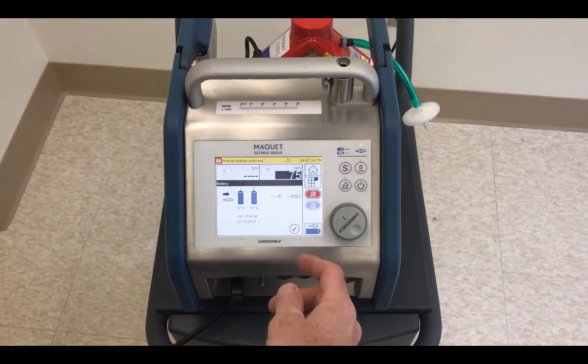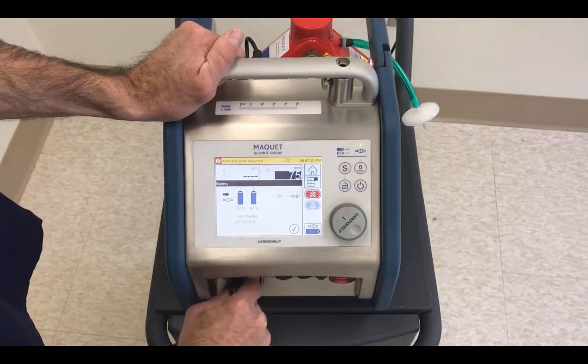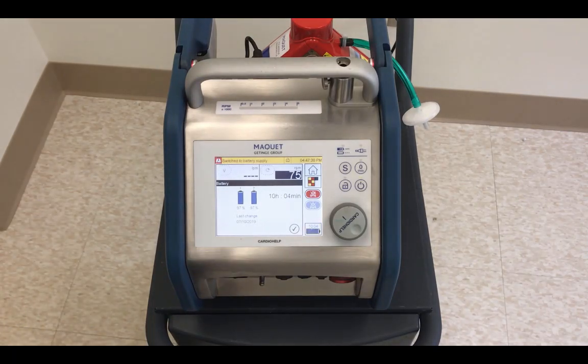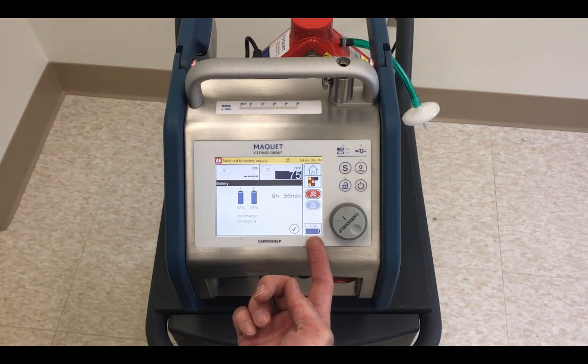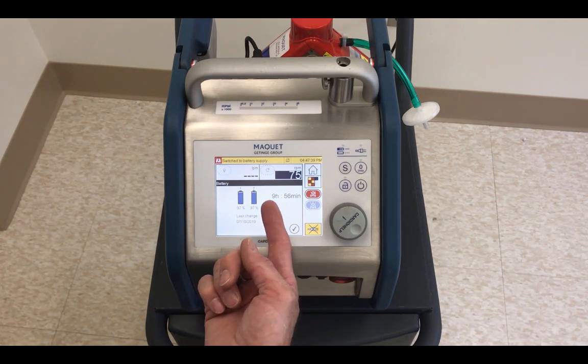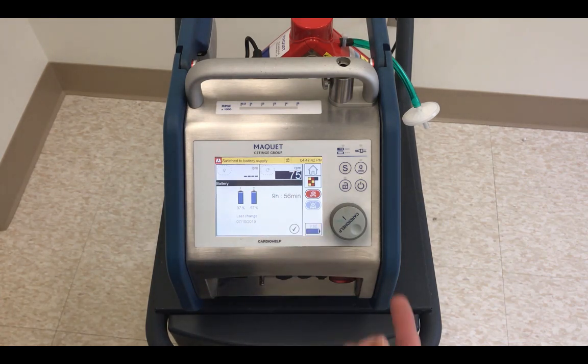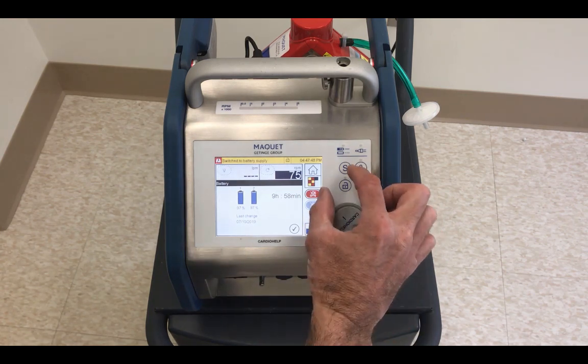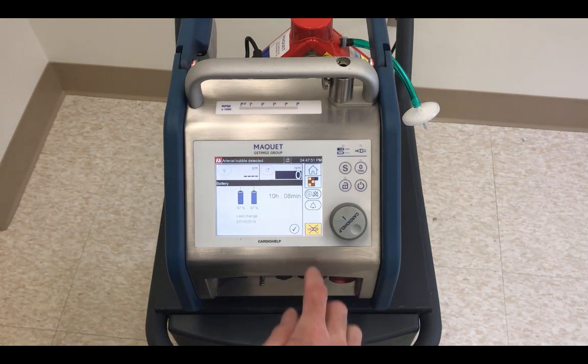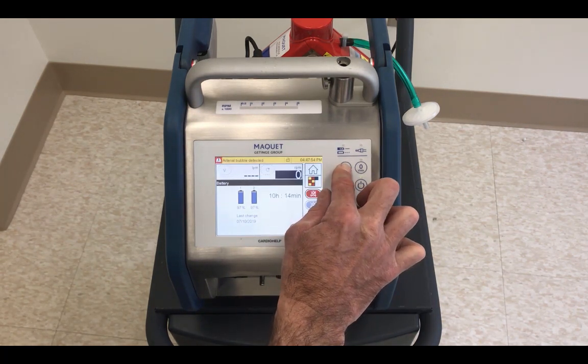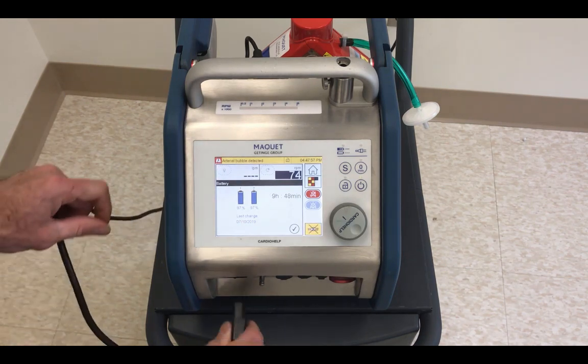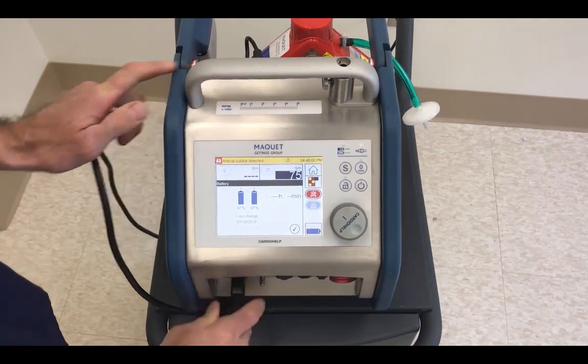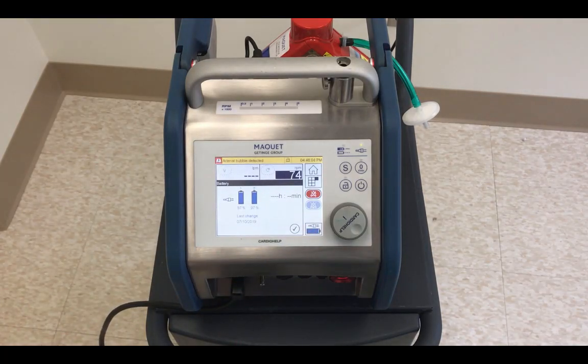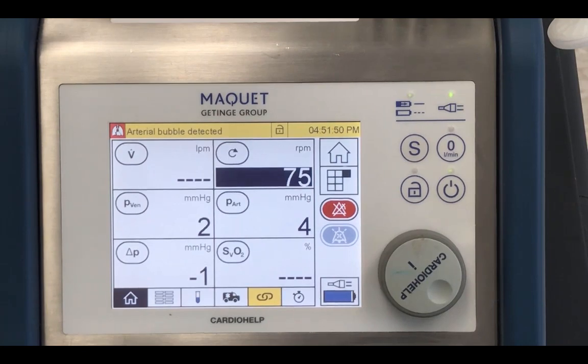Let's take a look at how this screen changes when we unplug it. Now we can see the icon is flashing, that we are not plugged into the wall, and it's giving us an estimate of 9 hours and 56 minutes of battery power, given that we're only pumping at 75 RPMs. There would be audible alarms, except that we've done the 2-finger. There we go. And when you're in global override, it's not going to tell you about these things. Plug it back in, and it will immediately correct itself. Let's close that window.